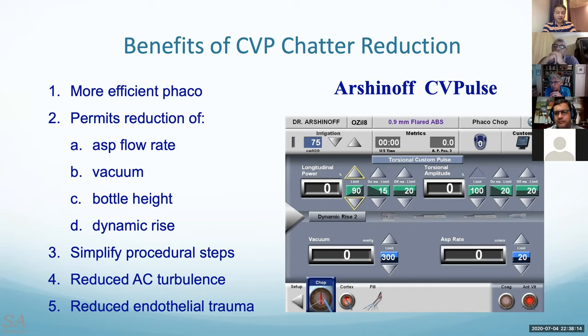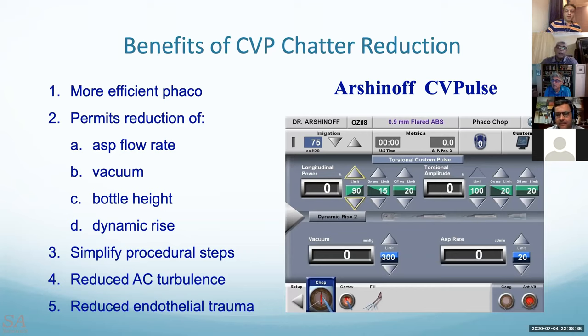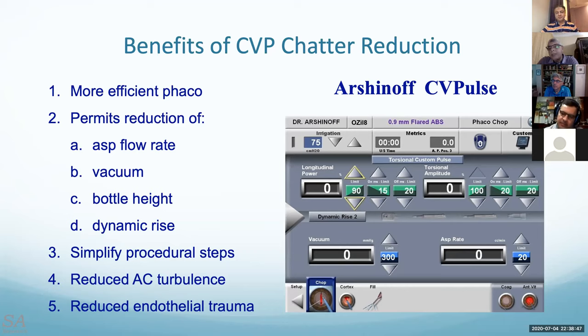On the Infinity, click the torsional custom pulse option on the menu and all the adjustment boxes come up to play with. The most important point about the Infinity is the torsional power — it's very helpful. You have to use both torsional and longitudinal. IP (Intelligent Phaco) on the Alcon machine kicks in when torsional gets caught, building vacuum to a point beyond what the machine wants. When the torsional isn't adequate to emulsify, IP gives a burst of three to five axial pulses to get you out of trouble.